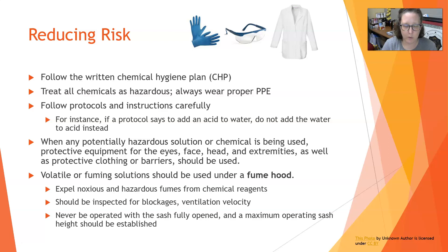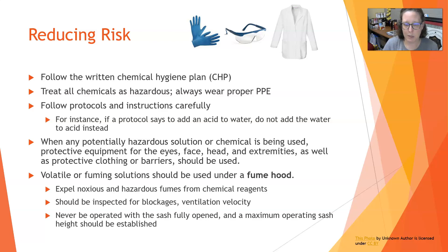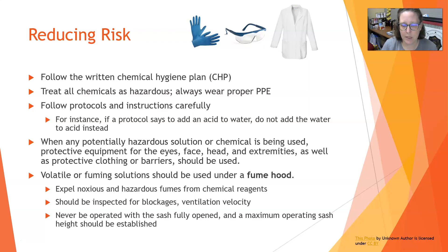Fume hoods help expel noxious and hazardous fumes away from you. They should be inspected for blockages and ventilation velocity — make sure nothing impedes the airflow pulling those fumes. A fume hood should never be operated with the sash fully opened, as that prevents proper suction. A maximum operating sash height should be established and never exceeded.